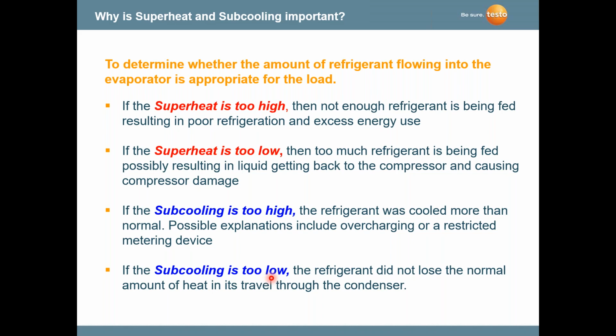If your superheat is too high, then not enough refrigerant is being fed, resulting in poor refrigeration or excess energy. If superheat is too low, too much refrigerant is being fed into the system, resulting in liquid getting back into the compressor and causing issues. If subcooling is too high, the refrigerant was cooled more than normal. If subcooling is too low, the refrigerant did not lose the normal amount of heat traveling through the condensing unit.